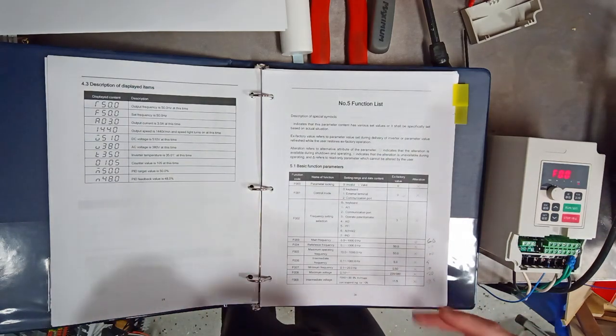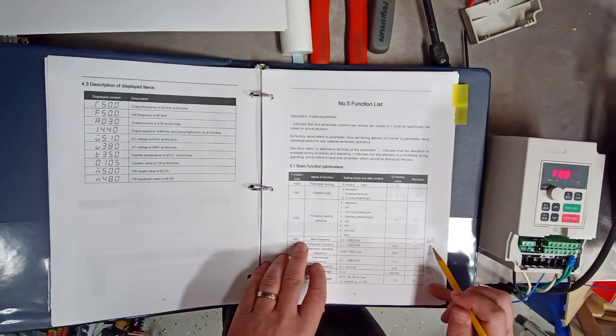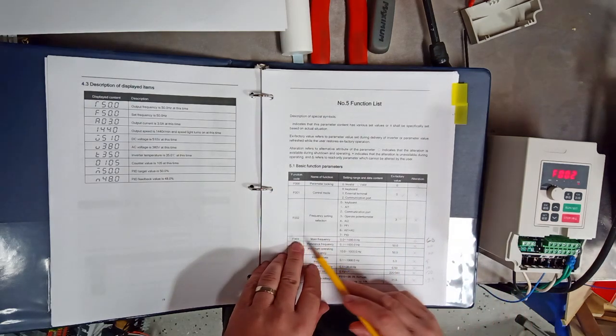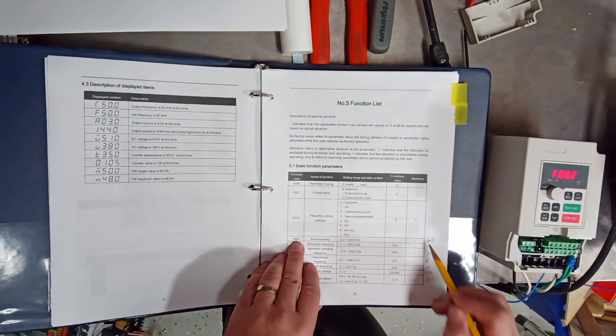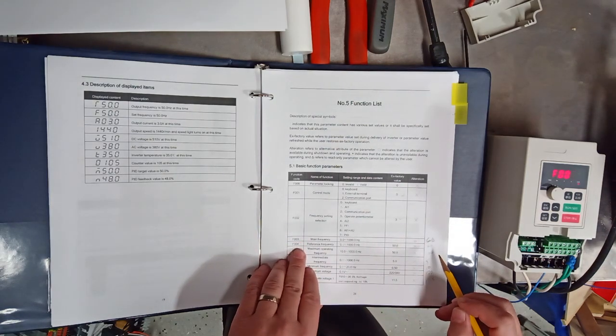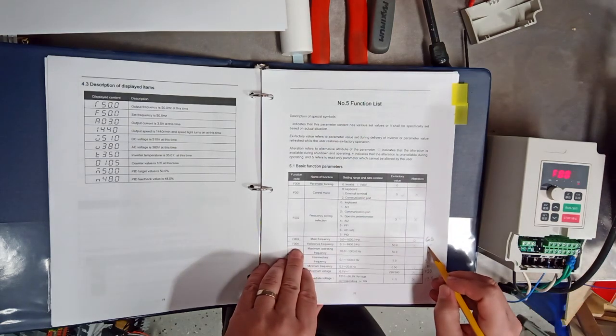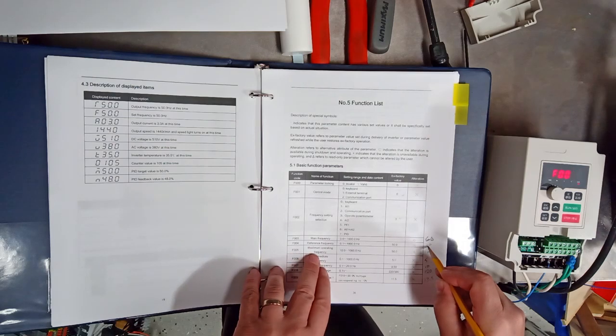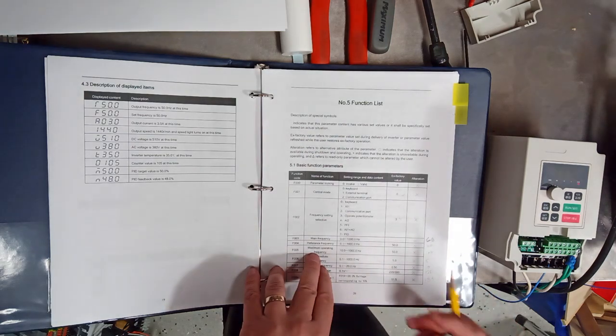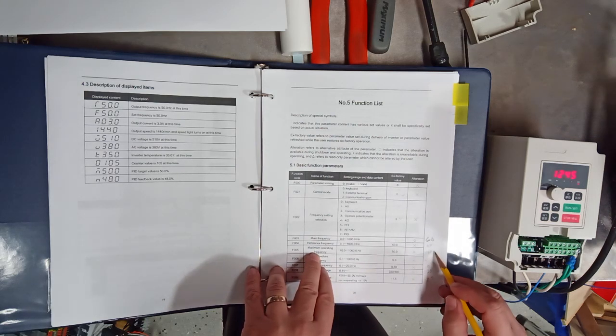How did I set this VFD to run this motor? The main thing that I end up doing is saying, OK, my main frequency, F03, is 60 Hz. So I want to make sure that I'm set for 60 Hz there. My reference frequency that is coming in is 60 Hz. I also do that at 60 Hz. My maximum operating frequency, because I'm using the 1750 RPM, I want to be able to run it up to as high as 100 Hz. That'll give me just about 3,000 RPM to be able to speed it up. If you're using the 3600 RPM, I think you'd leave that at 60 Hz.